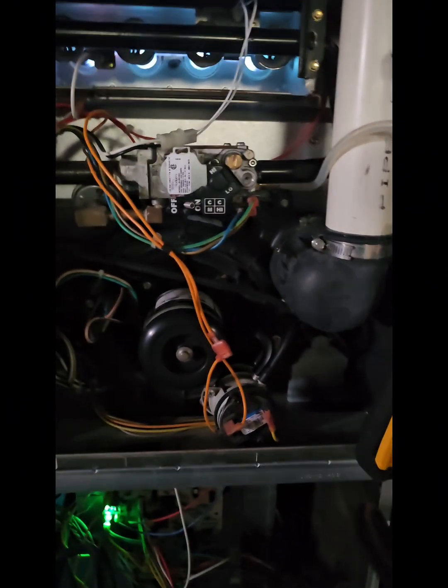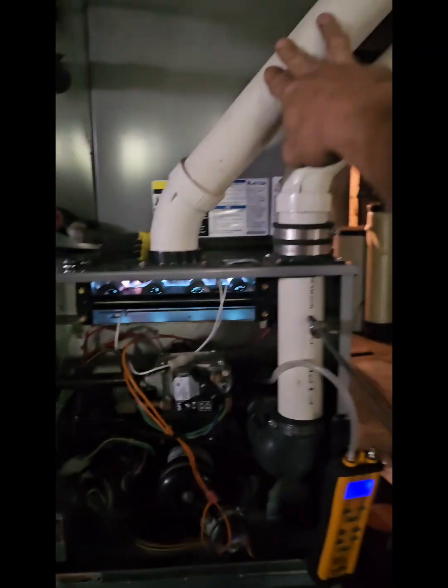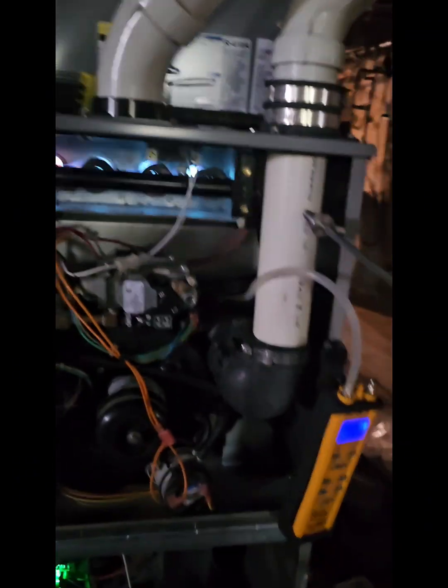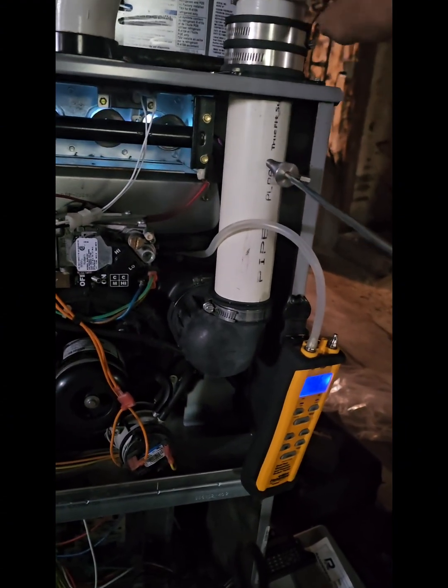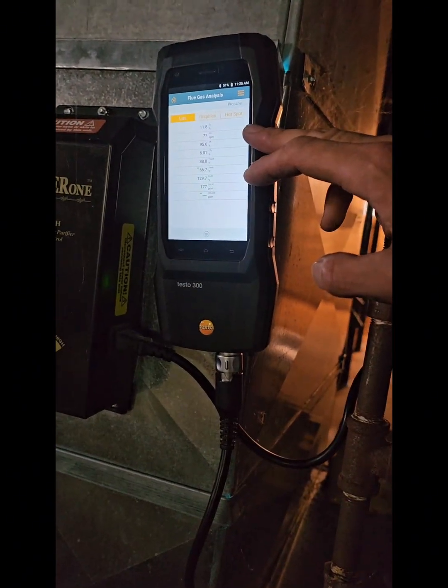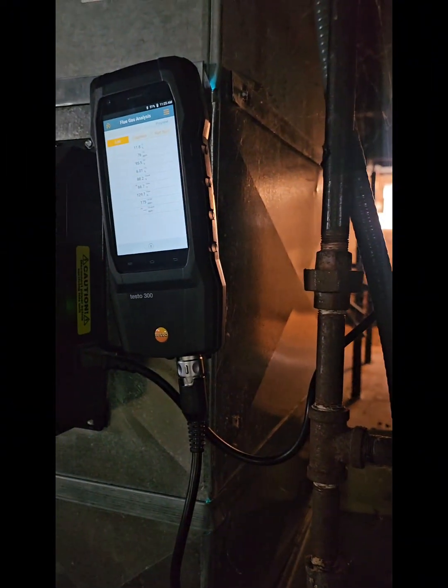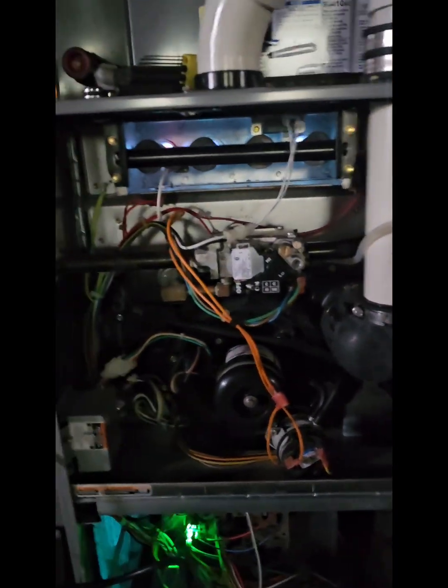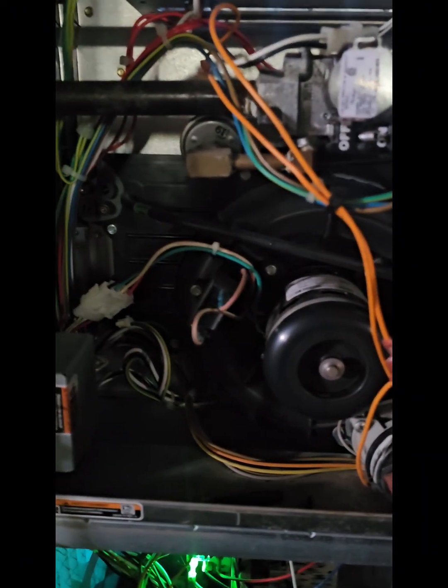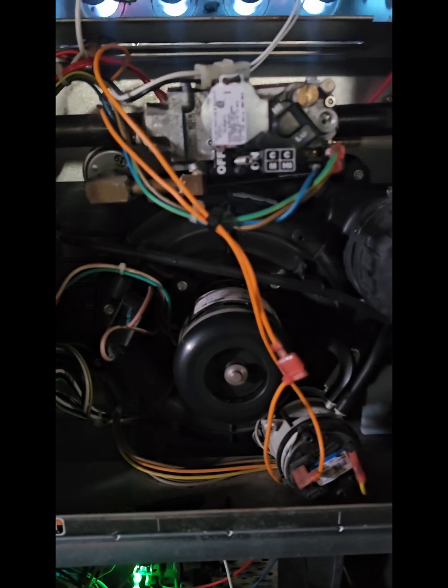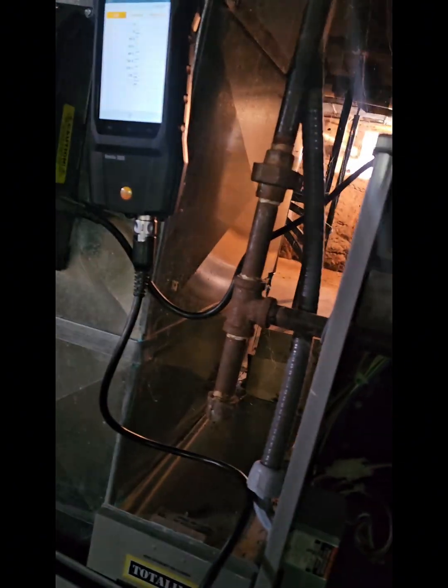With these combustion analyses, with the front cover off, we would be able to rule out any restrictions in the intake. Not quite sure. Can't say 100% about a restriction in the exhaust, but being that it has dropped below 100, that's a big enough drop to assume that there's no restrictions within the exhaust pipe here. So as long as our inducer is pulling a strong enough vacuum, everything but the heat exchanger can be ruled out.